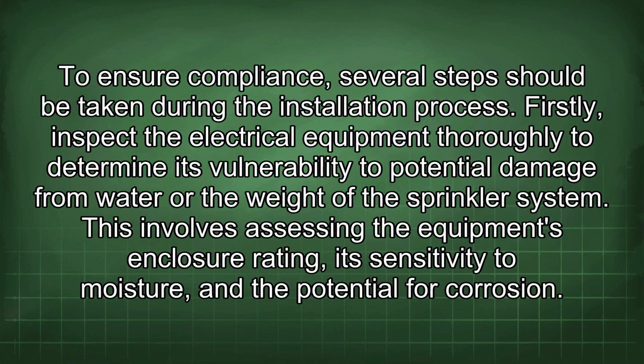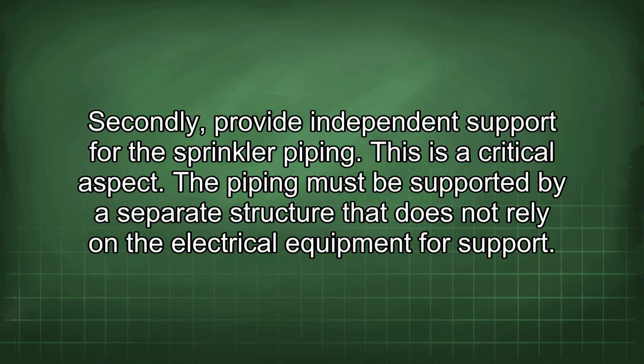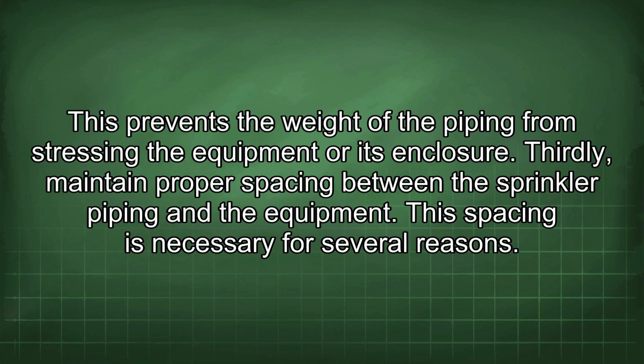To ensure compliance, several steps should be taken during the installation process. Firstly, inspect the electrical equipment thoroughly to determine its vulnerability to potential damage from water or the weight of the sprinkler system. This involves assessing the equipment's enclosure rating, its sensitivity to moisture, and the potential for corrosion. Secondly, provide independent support for the sprinkler piping. This is a critical aspect. The piping must be supported by a separate structure that does not rely on the electrical equipment for support. This prevents the weight of the piping from stressing the equipment or its enclosure.